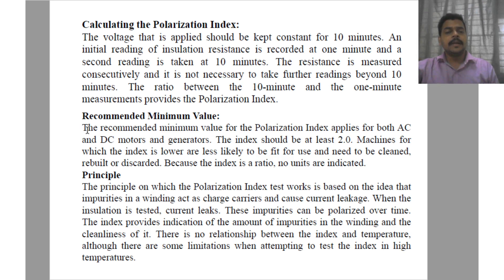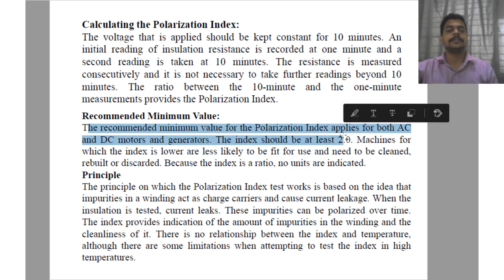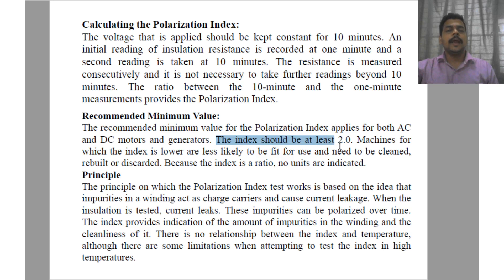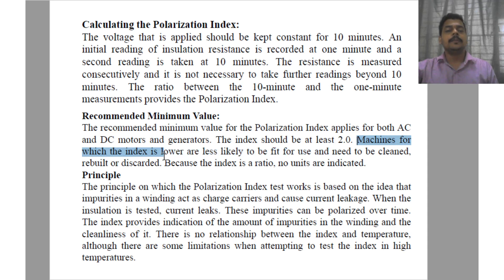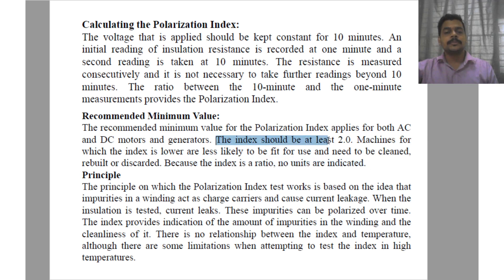The recommended minimum value of the polarization index applies for both DC and AC motors and generators. The index should be at least 2.0. Machines for which the index is lower are less likely to be fit for use and need to be cleaned, rebuilt, or discarded. Because the index is a ratio, no units are indicated.